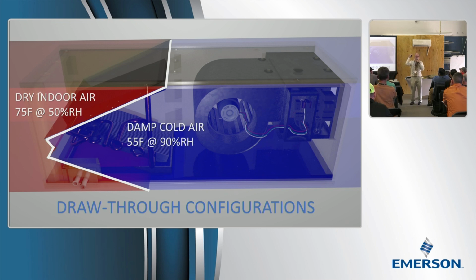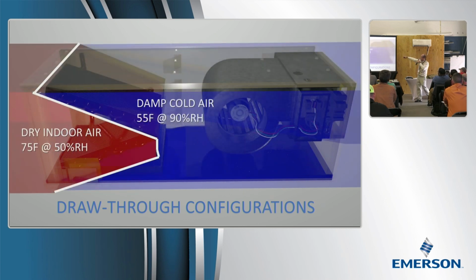Remember how we had an indoor dew point at 55 degrees? You have the same dew point right on through here. It drops a little bit at the coil, but you're at the indoor range of dew points. But this is cold air, and so this part of the cabinet wants to sweat. Whereas this A coil has return air up to that point. You should not get any sweat on the back of that. But remember, coils flip. So you flip the coil. Now it's going to be cold all the way to the back just by the configuration. So they don't all sweat the same.